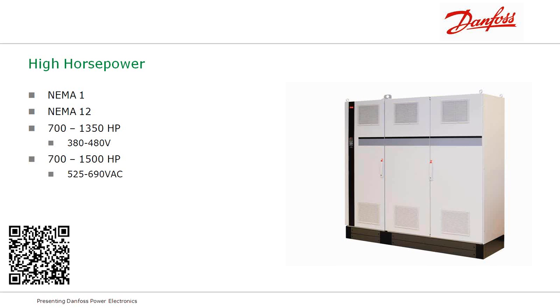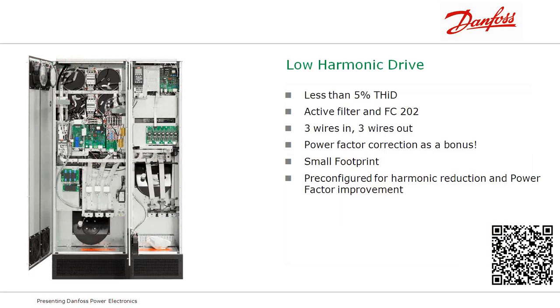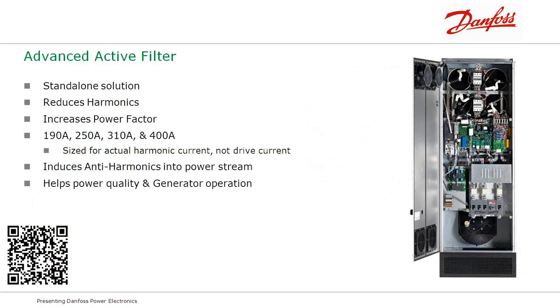Our higher horsepower product line has been out for about 5 or 6 years now. This starts at 700 horsepower. This is a parallel inverters. And then as some of the newer innovations we've come up with, this is the low harmonic drive. This is actually a drive mounted here on the right, mated up next to an active filter on the left. 3 wires in, 3 wires out.